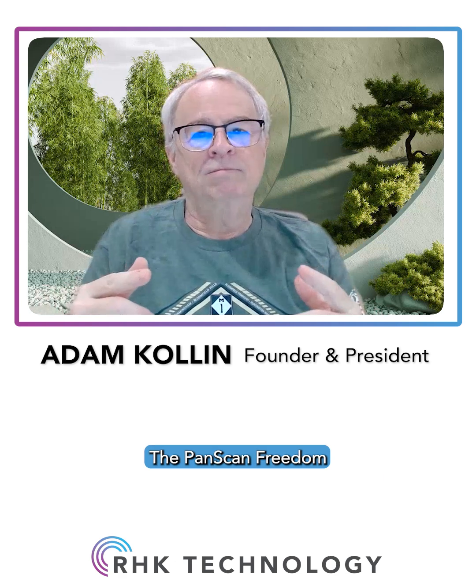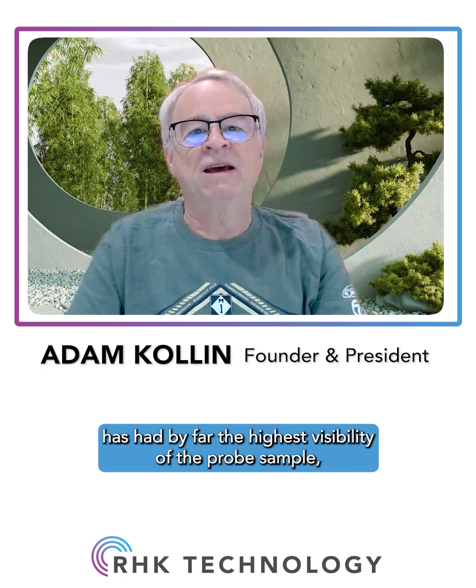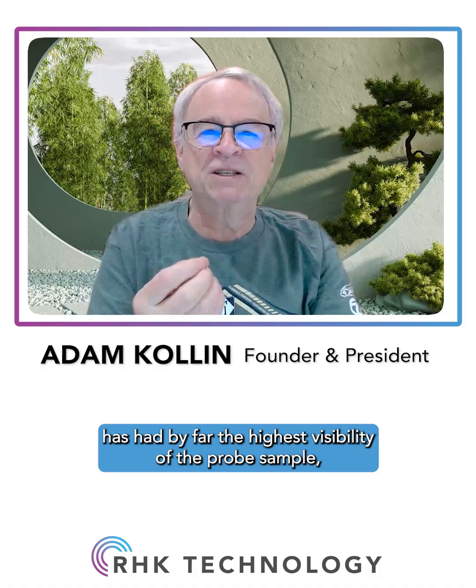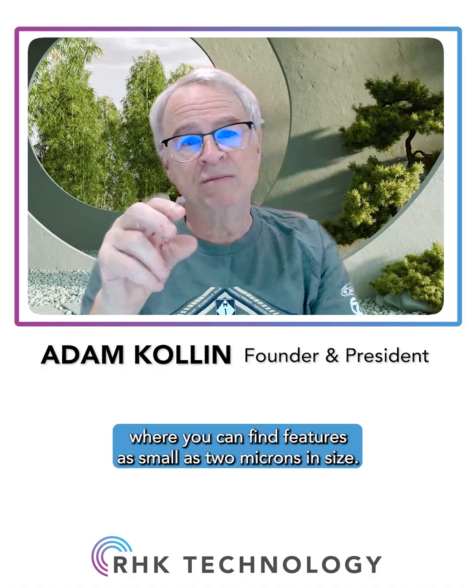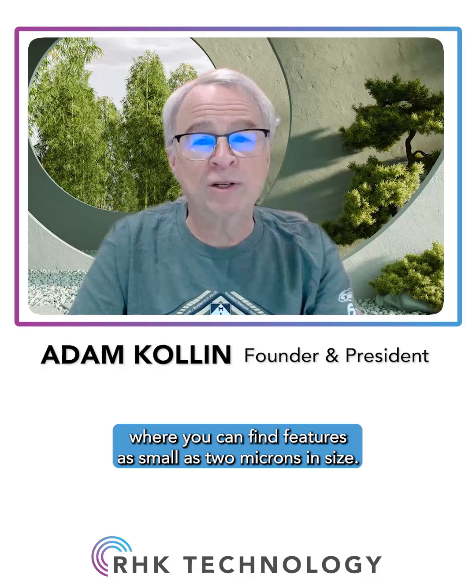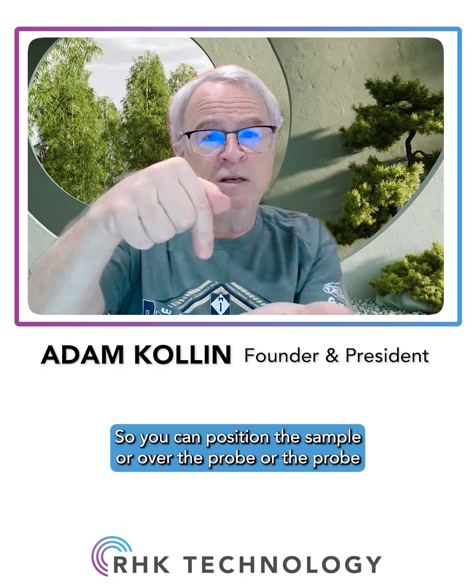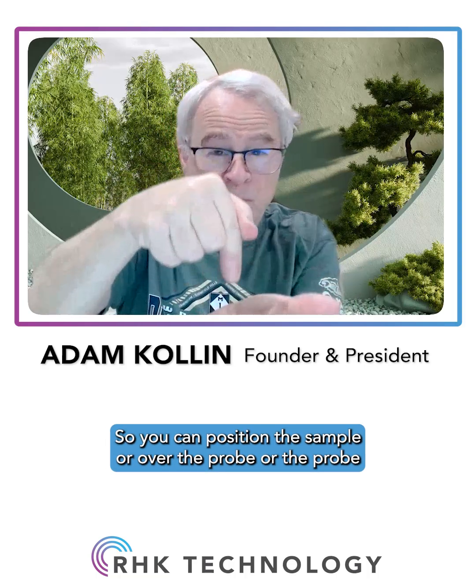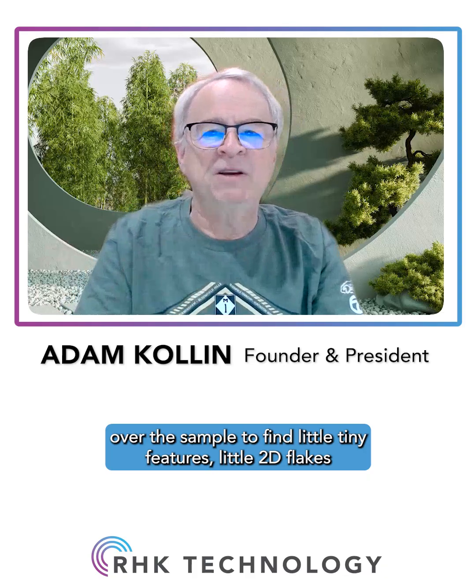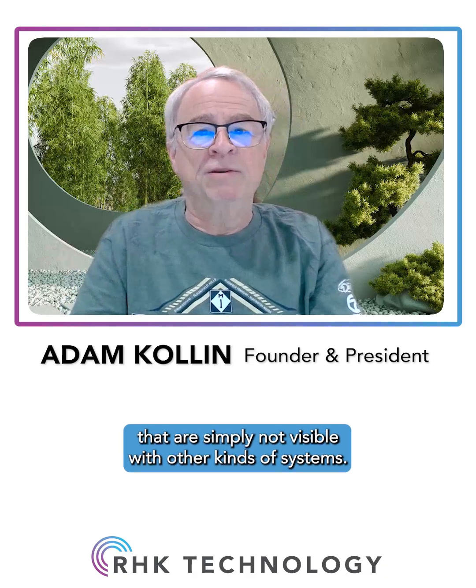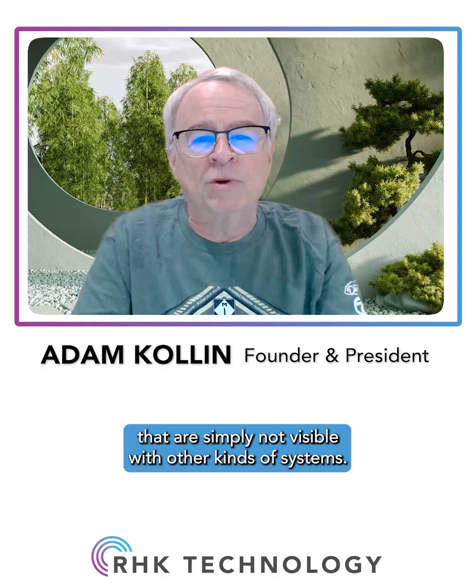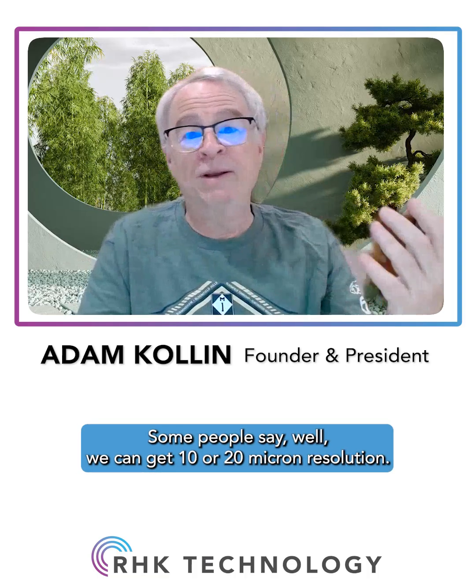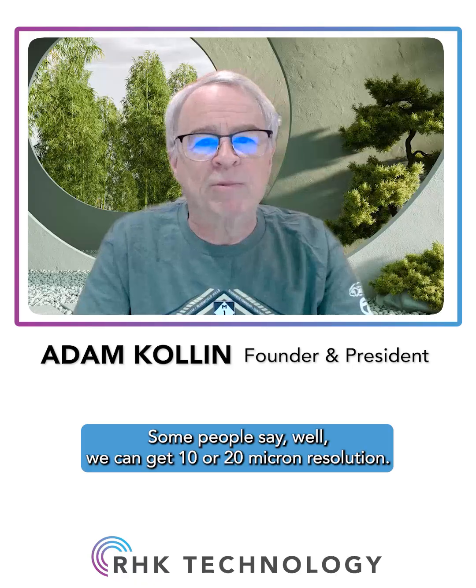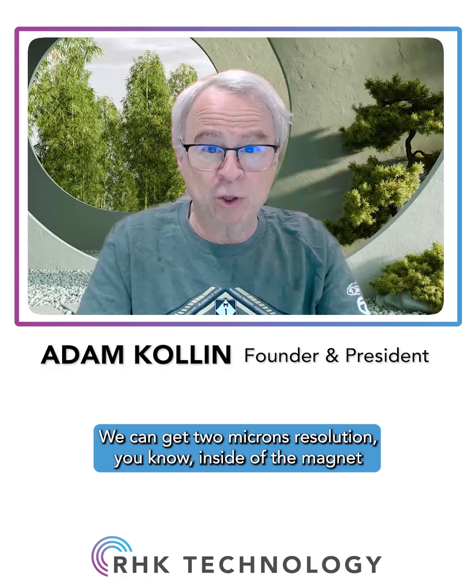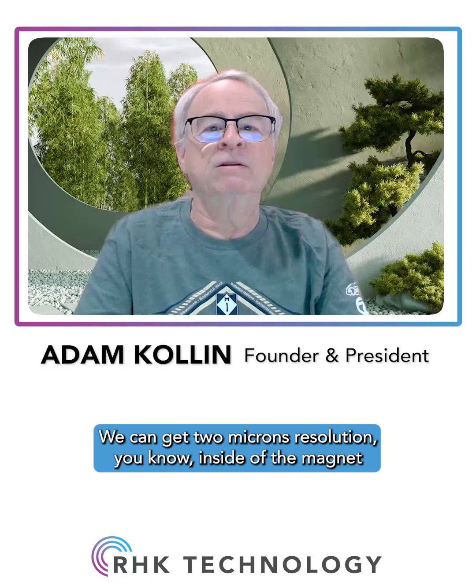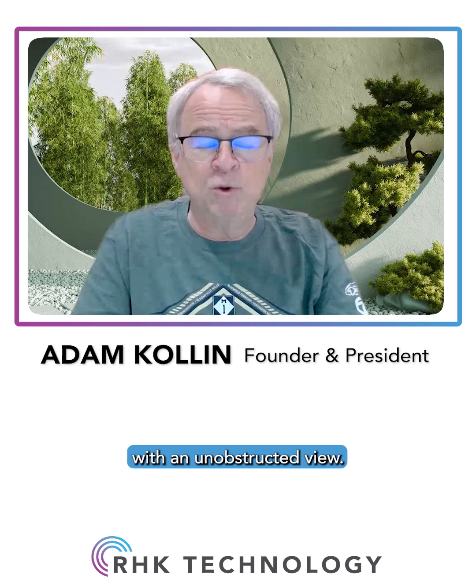So we can still, inside of a high magnetic field, get the high light collection efficiency. The PanScan Freedom has had by far the highest visibility to the probe sample, where you can find features as small as 2 microns in size. So you can position the sample over the probe or the probe over the sample to find little tiny features, little 2D flakes that are simply not visible with other kinds of systems. Some people say, well, we can get 10 or 20 micron resolution. We can get 2 microns resolution, inside of the magnet with an unobstructed view.